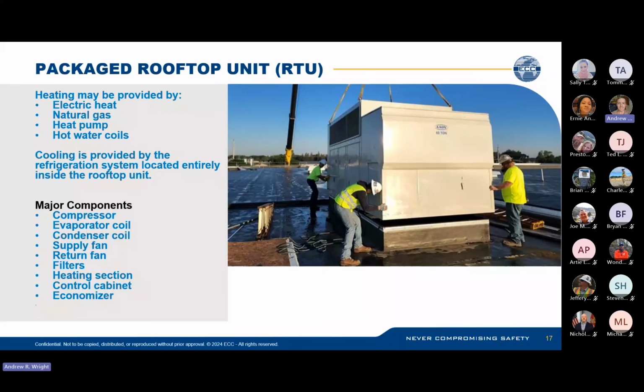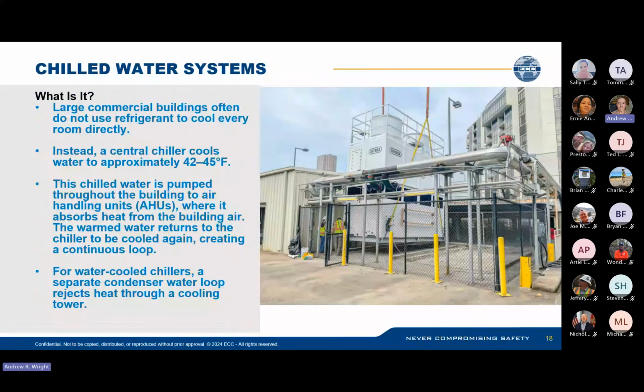Chilled water systems. I call them chillers. What is it? Large commercial buildings often don't use refrigerant to cool every room directly. Instead, a central chiller will cool water to around 42 to 45 degrees. The chilled water is pumped throughout the building to air handling units, where it absorbs heat from the building air. The warmed water returns to the chiller to be cooled again, creating a continuous loop. For water-cooled chillers, a separate condenser water loop rejects heat through a cooling tower.